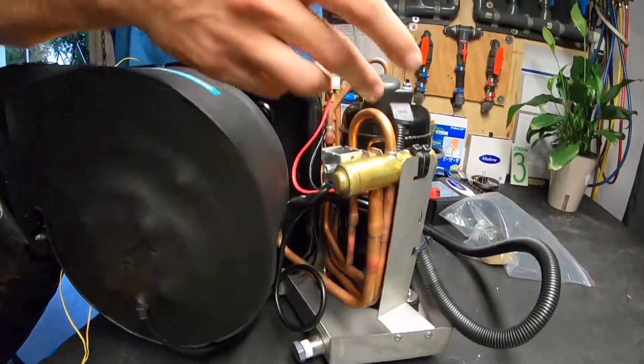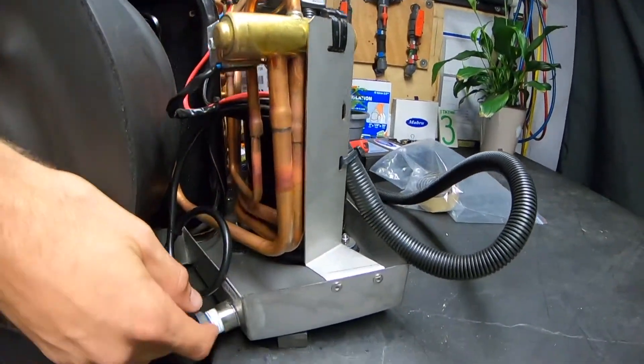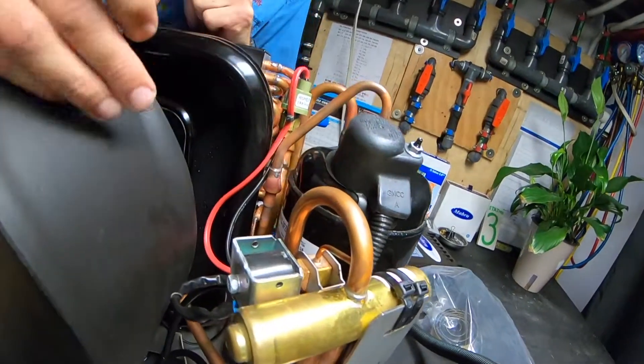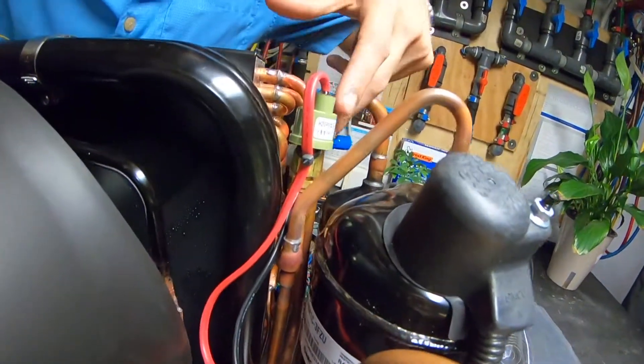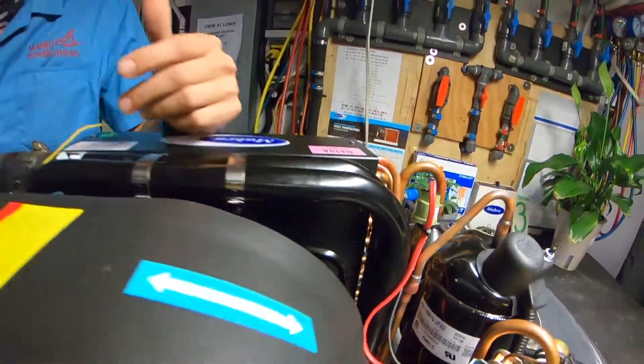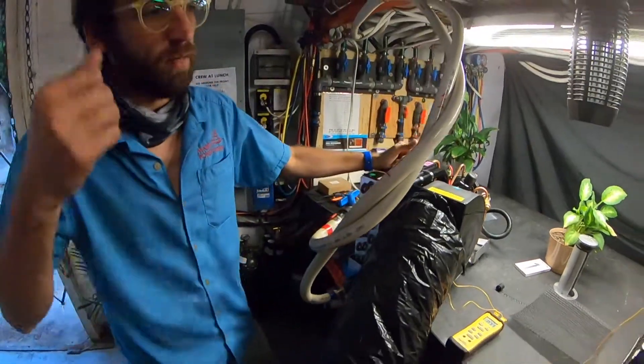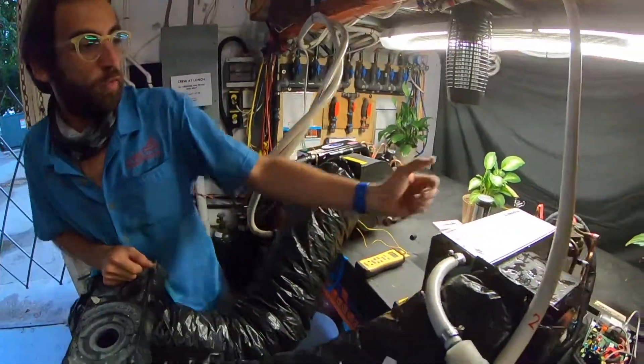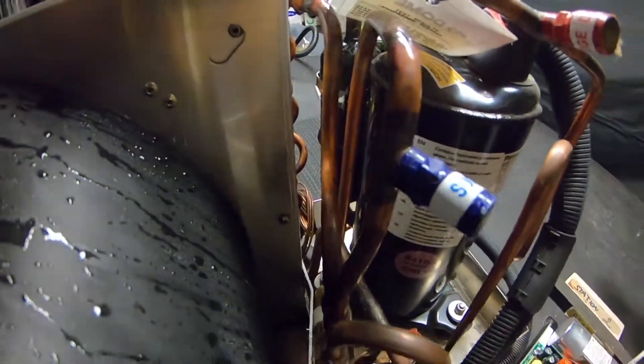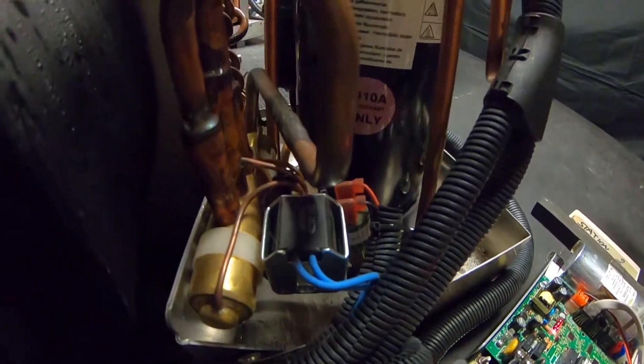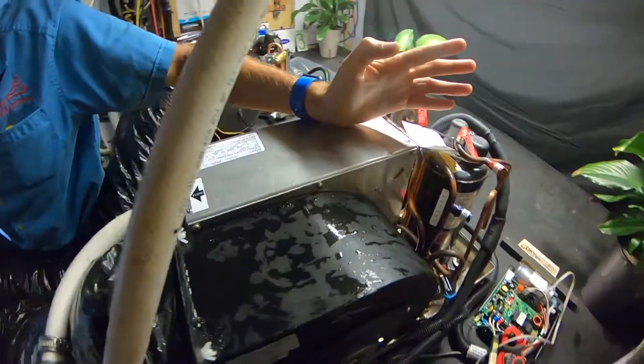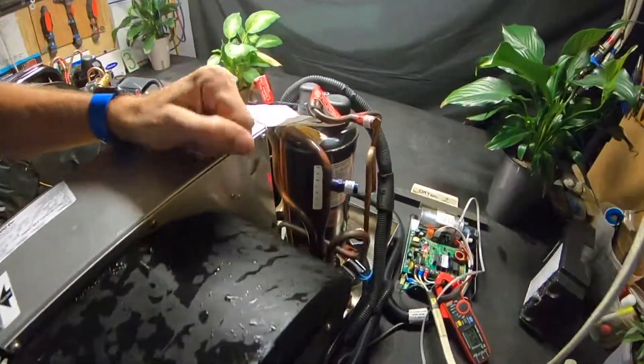Another thing to look at here is when we're looking at these welds. Look at the weld over here. When you're looking at all these welds, they're very clean welds. These are all done by CNC robotics. This is not something done by hand. It's not a person that's doing each and every weld. Although if you look over here, you can see that these welds do tend to be a bit sloppier. And these welds will vary from unit to unit. There's hot points. Where we do have the hot points, the cover is going to be a bit more brittle and more likely to have leaks.